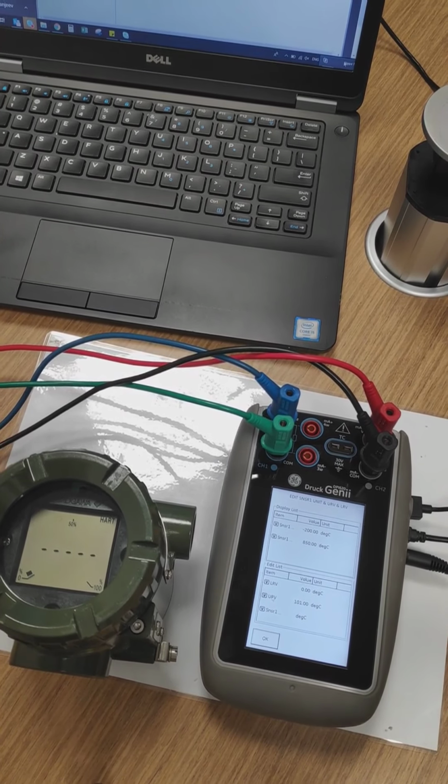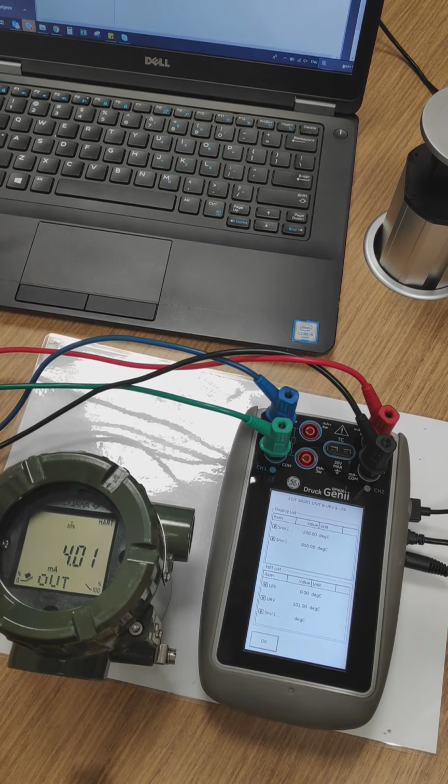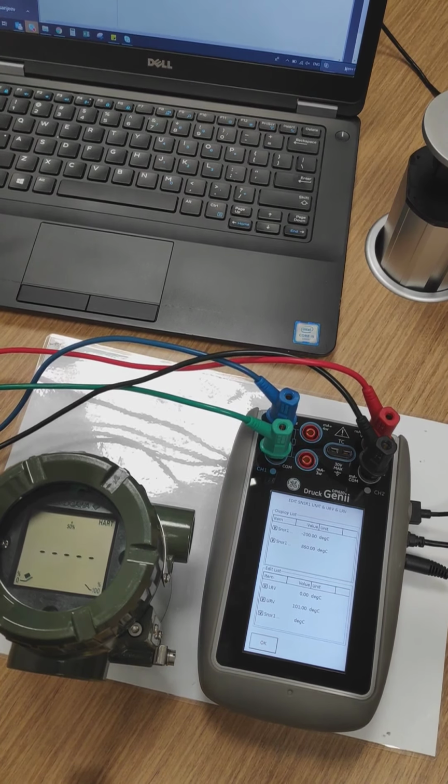That's why getting a calibrator like Genii with HART capability will allow us to do the calibration and communication in one shot, with no need for connecting and disconnecting. Also getting 4Sight, so we can set up the tolerance, will tell us if we have a pass or fail without needing a table, doing a calculation and calculating the error point by point. This will save us time, this will avoid human errors, and this will be all documented in the software, as the data stored on the Genie will go without any user interruption to the 4Sight.